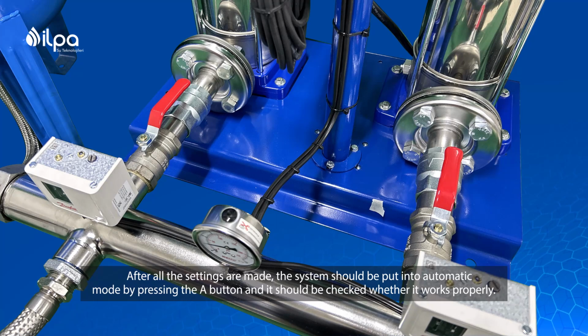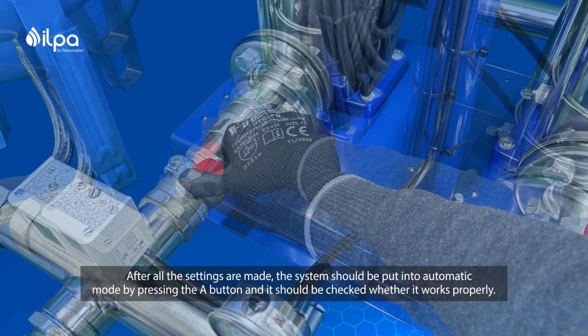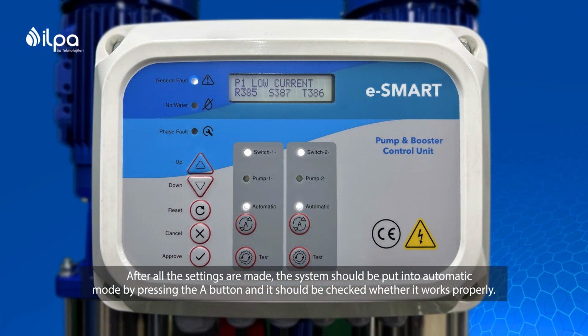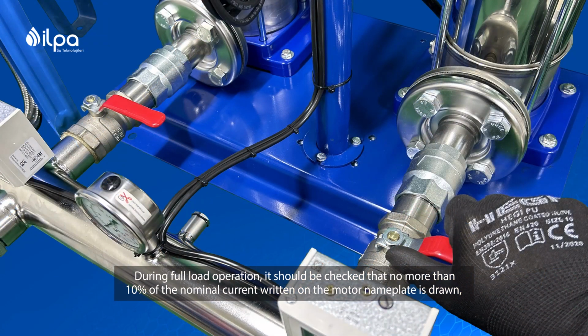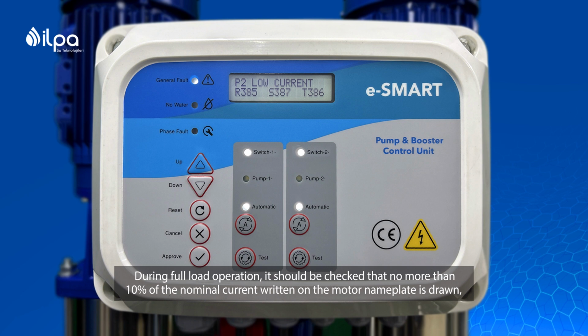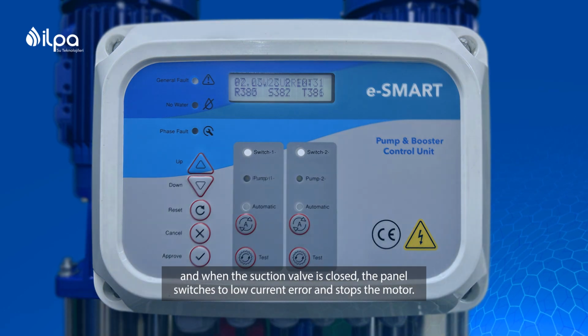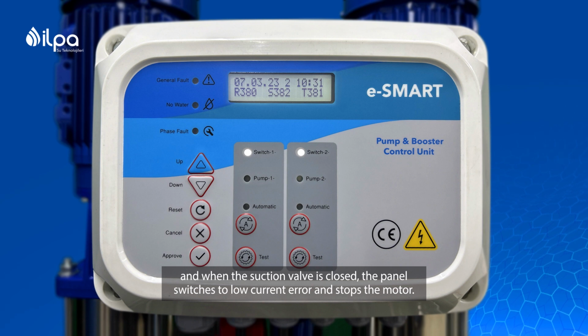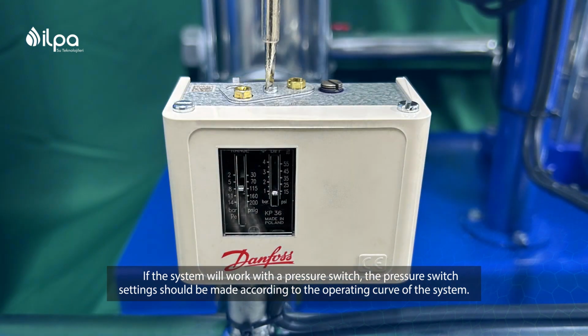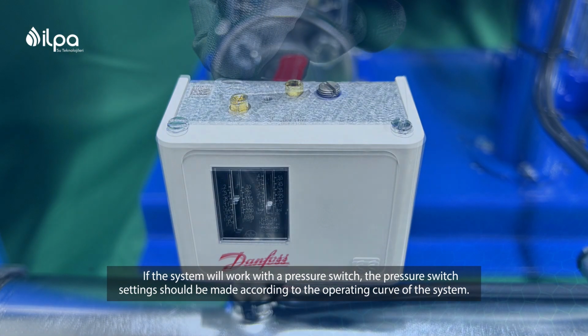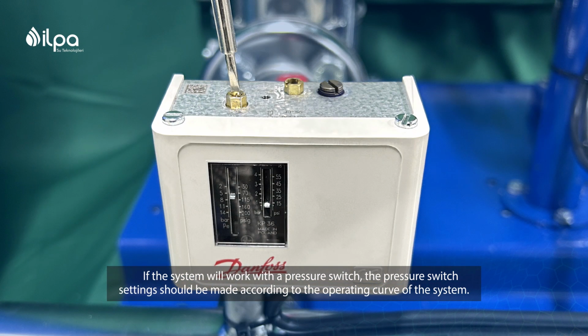After all the settings are made, the system should be put into automatic mode by pressing the A button, and it should be checked whether it works properly. During full load operation, it should be checked that no more than 10% of the nominal current written on the motor nameplate is drawn, and when the suction valve is closed, the panel switches to low current error and stops the motor. If the system will work with a pressure switch, the pressure switch settings should be made according to the operating curve of the system.